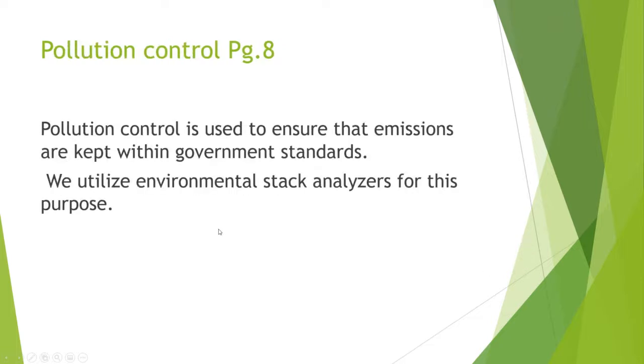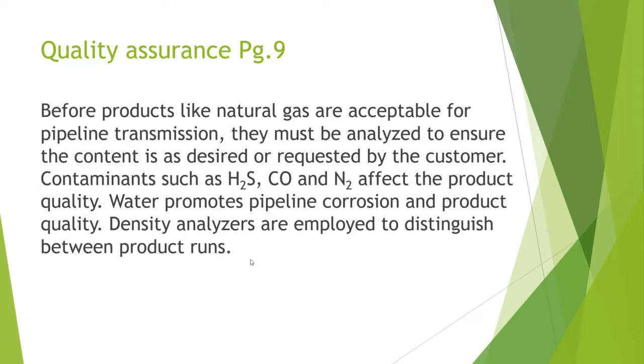The third application is pollution control, which is becoming increasingly important. Using these analyzers to ensure emissions are kept within government standards is the primary concern, and this ILM's focus on pollution is largely related to combustion. Fourth is quality assurance — specifically for natural gas and pipelines, the gas must be analyzed to ensure content is as desired by the customer. Contaminants such as H2S, CO2, and nitrogen affect product quality.